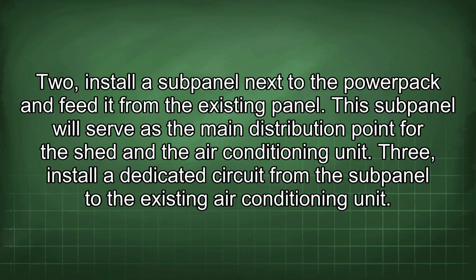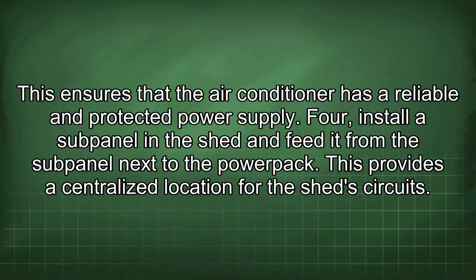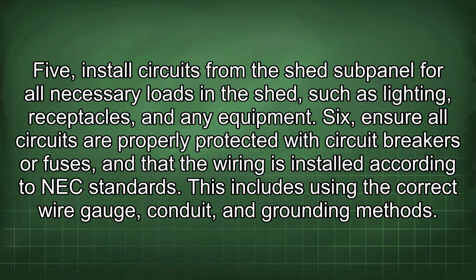3. Install a dedicated circuit from the subpanel to the existing air conditioning unit. This ensures that the air conditioner has a reliable and protected power supply. 4. Install a subpanel in the shed and feed it from the subpanel next to the power pack. This provides a centralized location for the shed circuits. 5. Install circuits from the shed subpanel for all necessary loads in the shed, such as lighting, receptacles, and any equipment. 6. Ensure all circuits are properly protected with circuit breakers or fuses, and that the wiring is installed according to NEC standards. This includes using the correct wire gauge, conduit, and grounding methods.